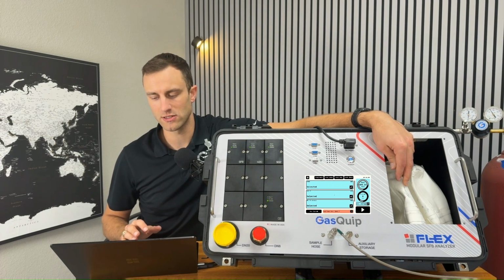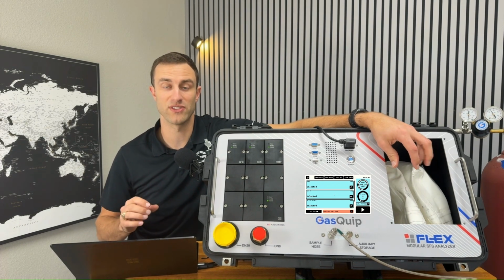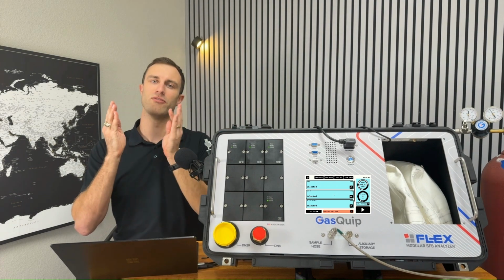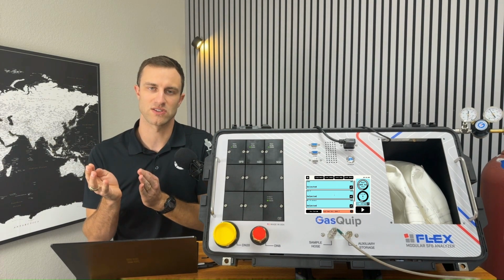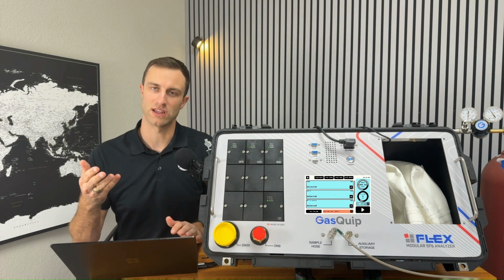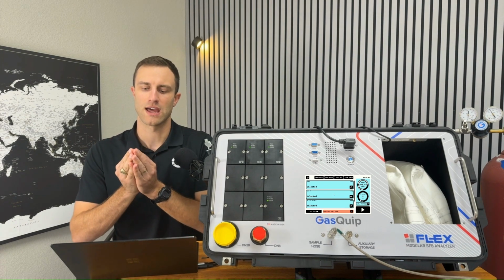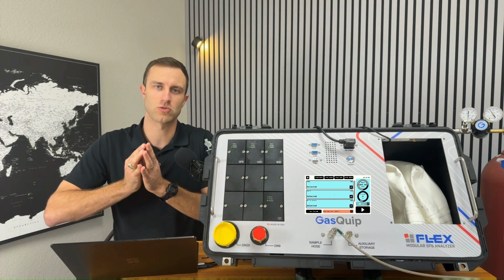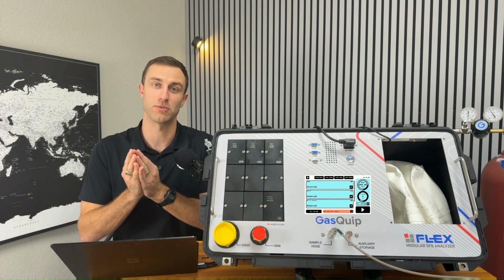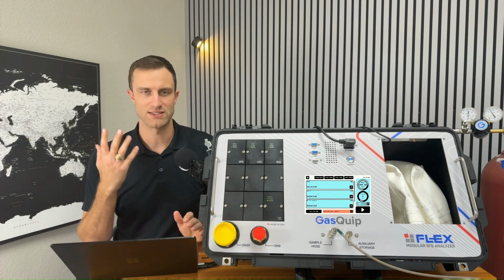So visually inspect the bag to make sure that it's inflating with gas and not staying in its vacuum down state after a pump back or an evac bag. It'll be really taut and tight, but you should see it start to inflate as an actual sample is being run. If you don't see that, the sample is not being run through the system.